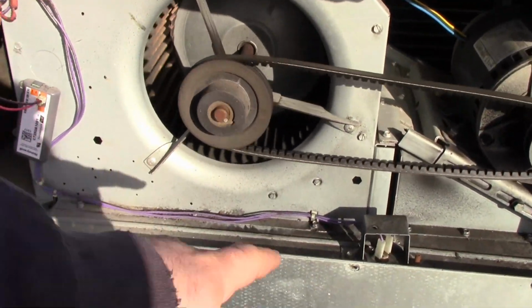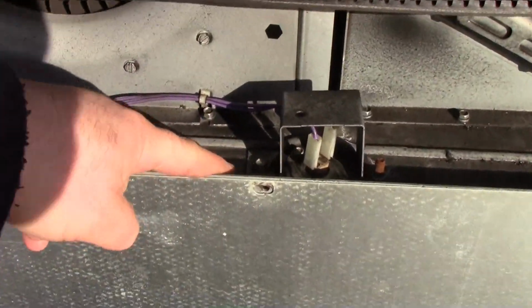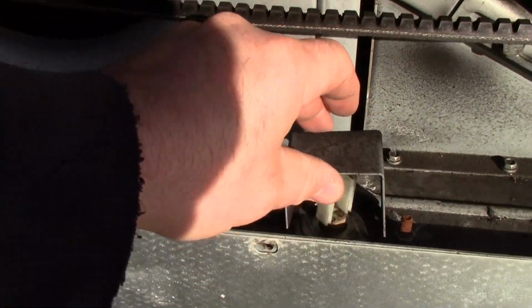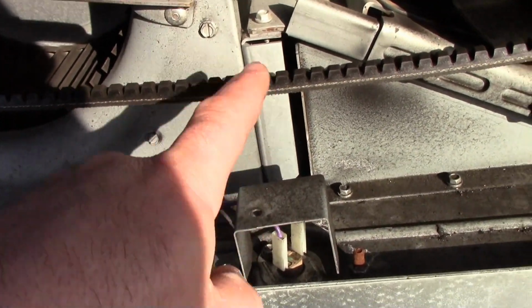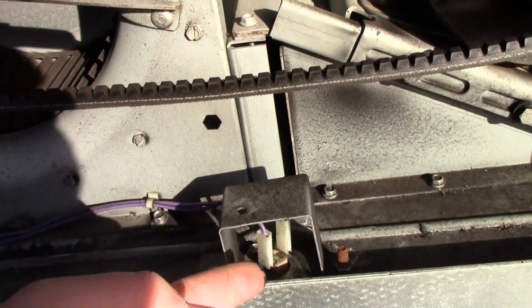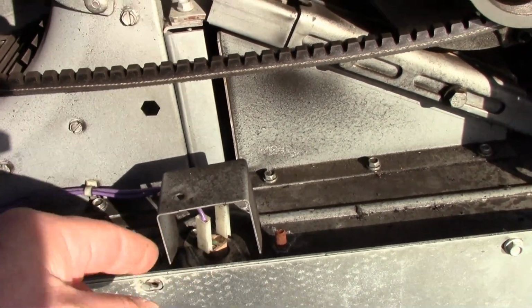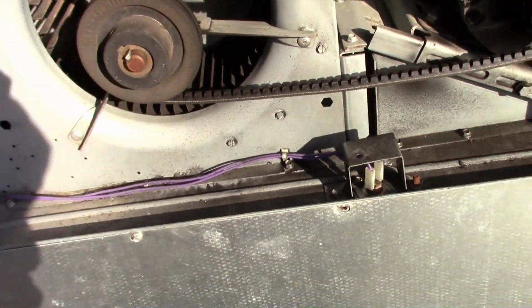I can shut the unit off, and all you got to do is take this little screw out here. This little protector comes off. This is so if this belt breaks, this belt doesn't come back around and whip this. Take this off and check between those terminals.